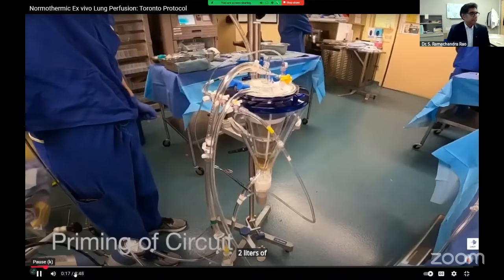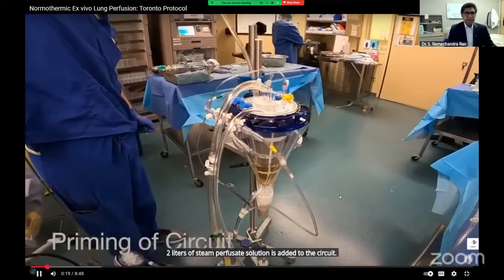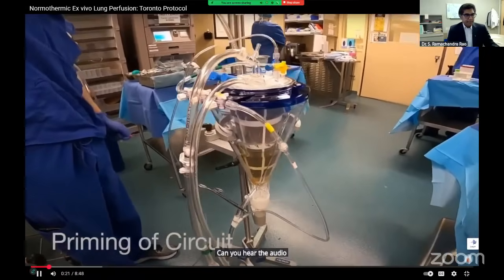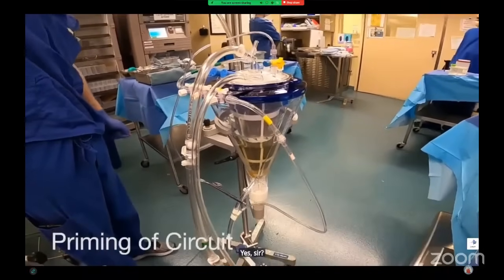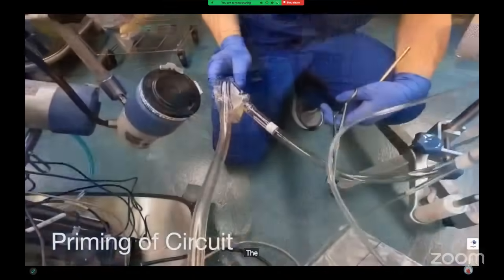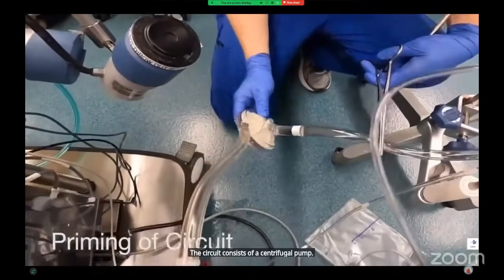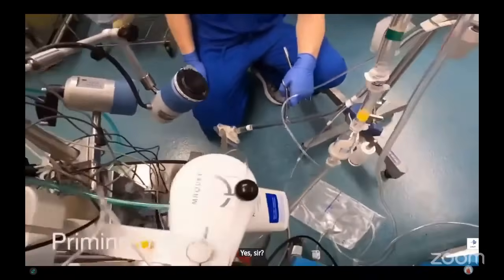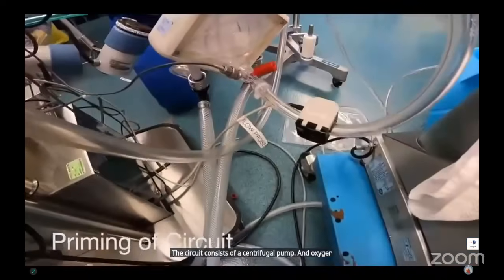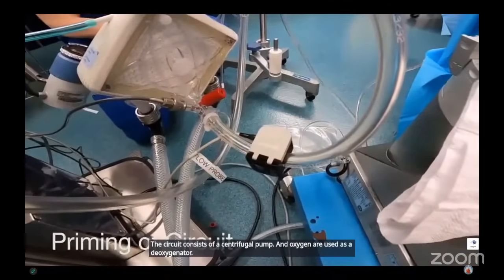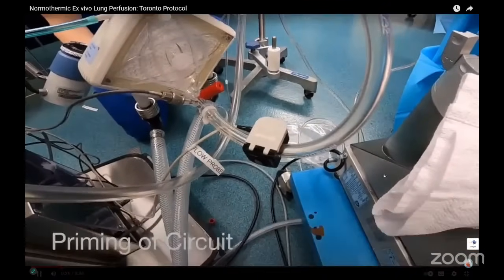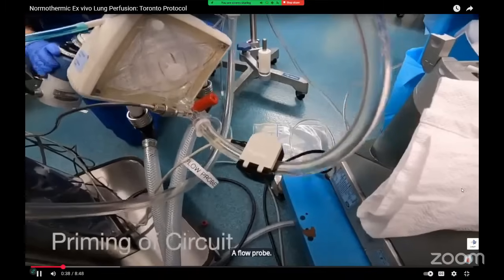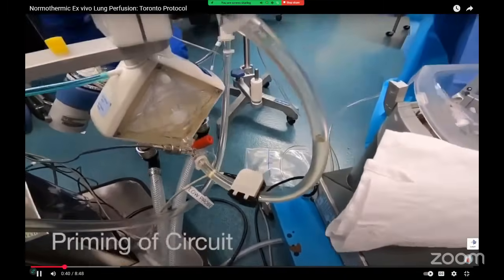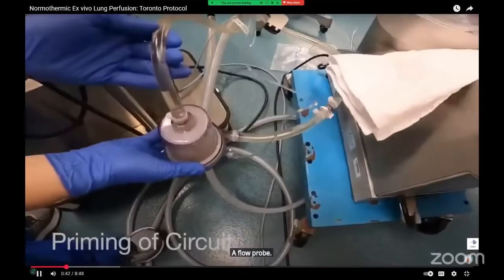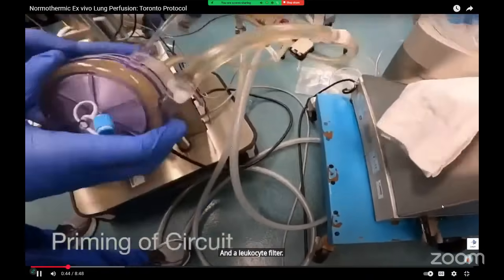We begin by priming the circuit. 2 liters of Steen perfusate solution is added to the circuit. Can you hear the audio? Yes, sir. Awesome. The circuit consists of a centrifugal pump, an oxygenator used as a deoxygenator, a flow probe, and a leukocyte filter.